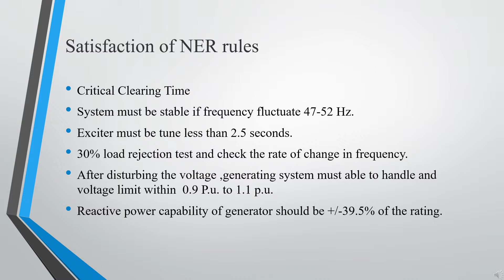After that, we had to check the reactive power capability of the generator, and it should exceed 39.5% of the generator rating. Here we can see the graph of the terminal voltage versus time of the exciter. We need the exciter for 5% overshoot and 5% settling time of 2 seconds. From the graph, we can calculate the settling time, which is 2.3 seconds, and as per the NER clause, it should be less than 2.5 seconds.